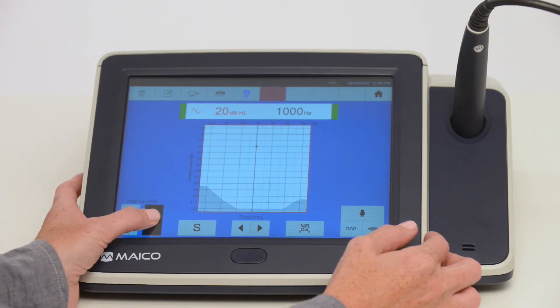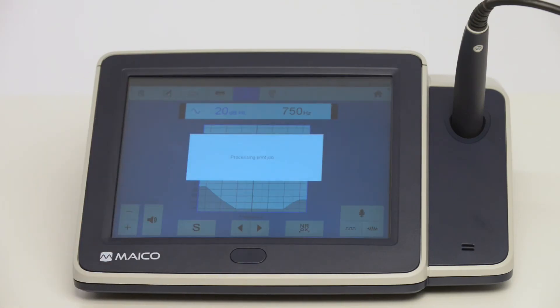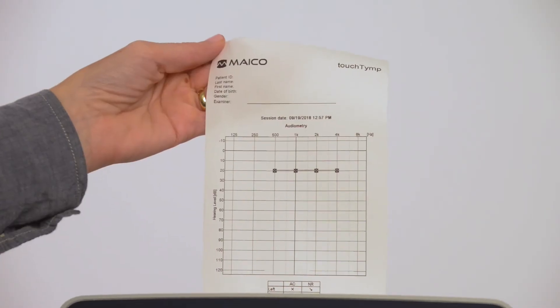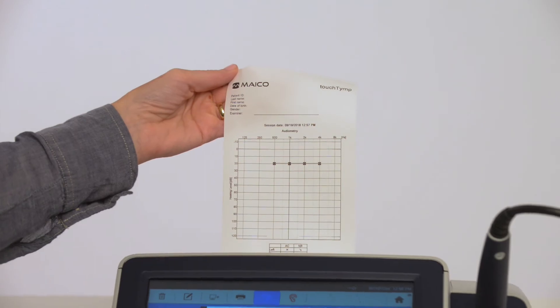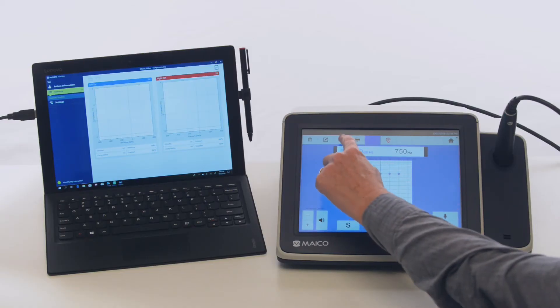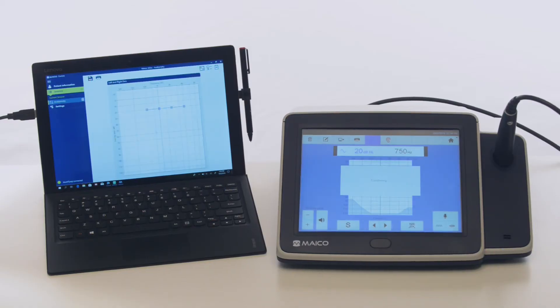Results can be stored on the device by pressing the S button. Final testing results can be printed by selecting the print button or transferred to a PC by pressing the transfer button. Transfer requires the touchTymp be connected to a PC with the Maico software open.